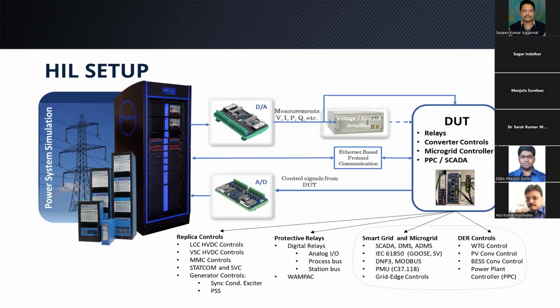So the setup will have a simulator with input-output cards, and your device under test. There can be any number of devices that can be tested through this method. Typically it is popular for testing HVDC replica controls using the RTDS simulator. Similarly, you can test converter controls, inverter controls, relays, and perform cybersecurity type applications using the HIL setup.